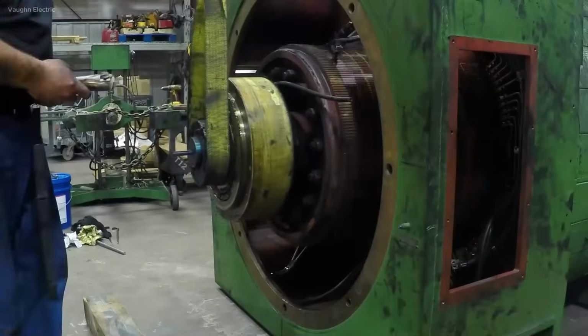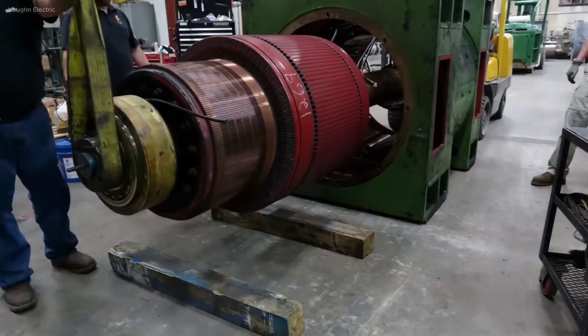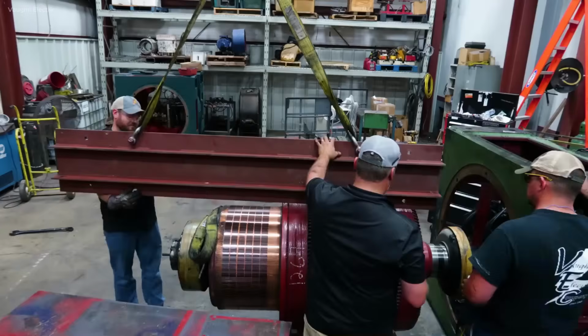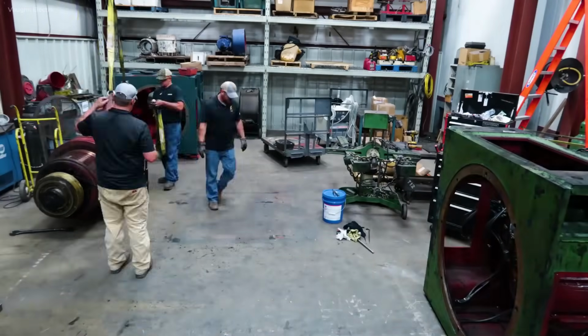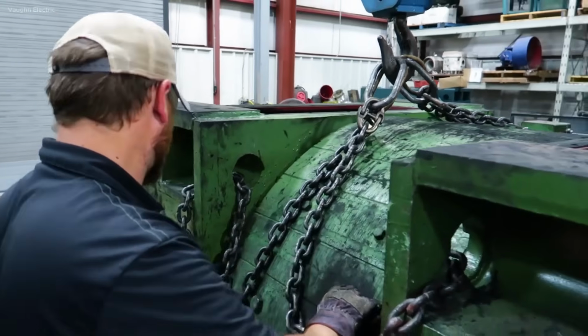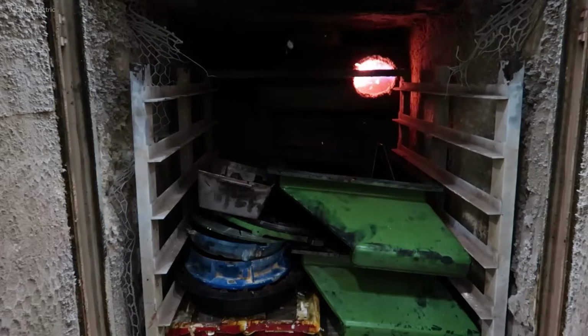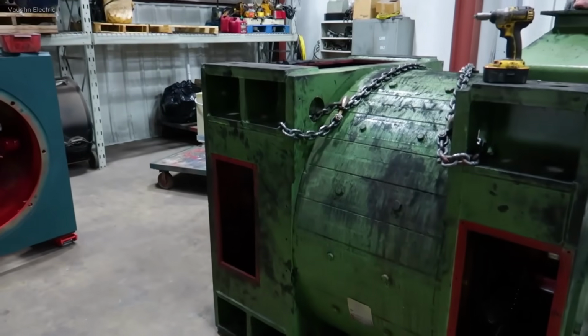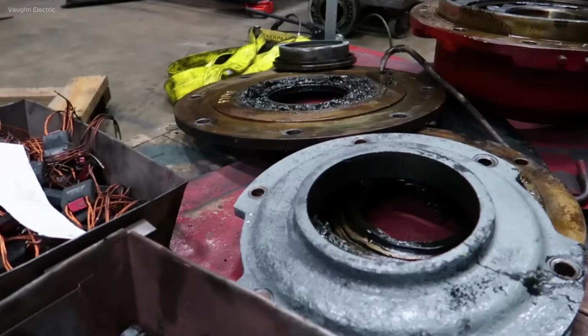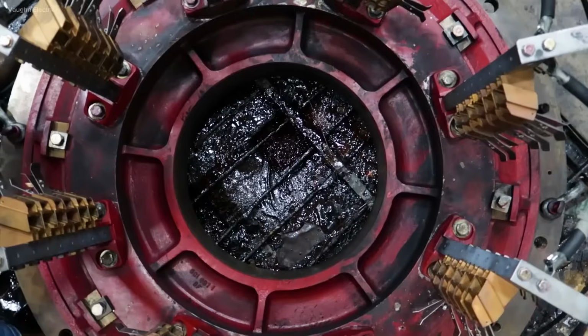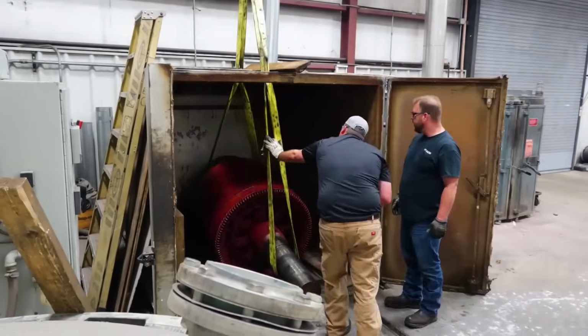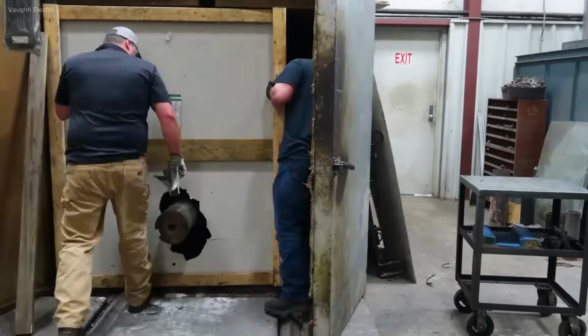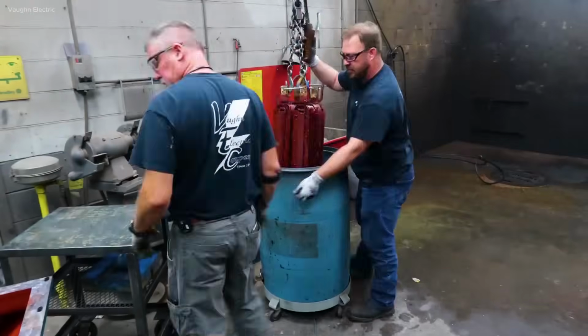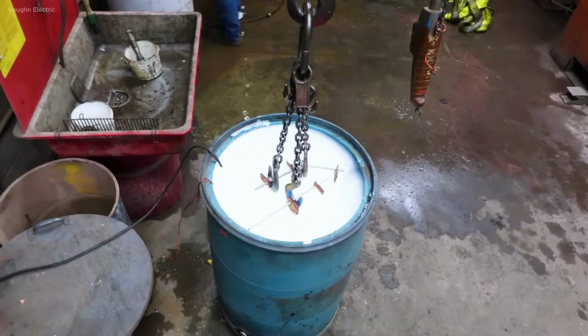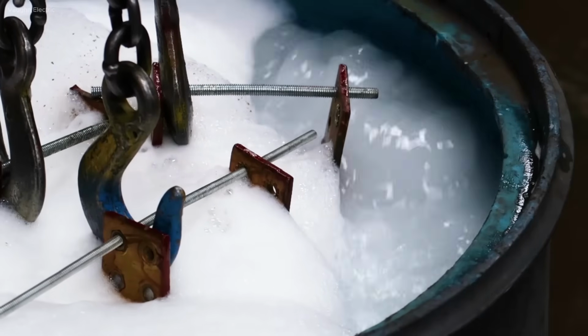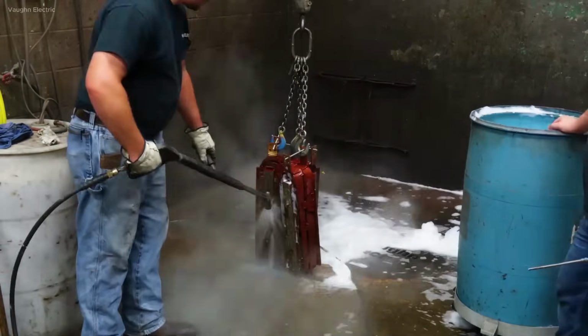Once disassembled, the rotor, stator, housing, and covers are thoroughly cleaned. The stator and rotor are initially degreased using high-pressure steam washers at approximately 180 degrees Fahrenheit to remove oil, dirt, and carbon buildup. For more stubborn contaminants, an alkaline soak or solvent bath is used. Compressed air at 90 to 100 psi is then applied to remove residual moisture and particles. Bearing housings and shaft ends are cleaned and checked for scoring or deformation using micrometers and bore gauges.